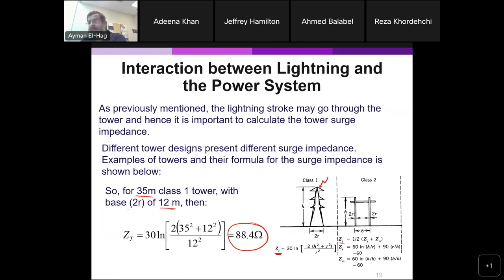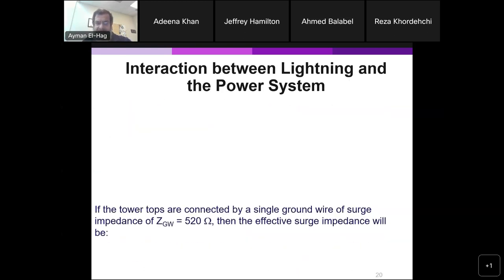Now the surge impedance is very, very important, because the surge impedance along with the impedance of the ground will tell you, for example, how much reflected wave there will be, and whether the wave will be negative or positive. Now the ZT doesn't change, because it is a characteristic of the structure itself. But we'll see in a few slides that there is another issue with the grounding resistance, which can change. It can start very high, or even if you start with a low foot resistance, it can change with time, as we will highlight briefly.